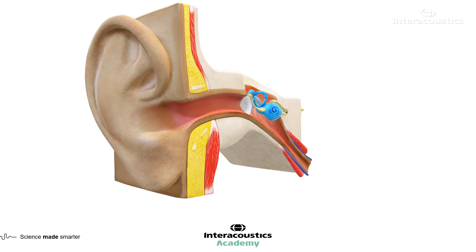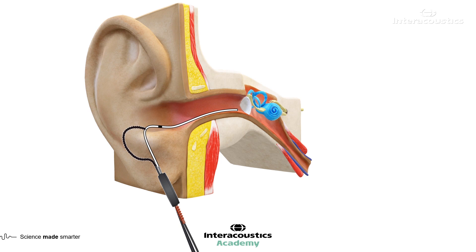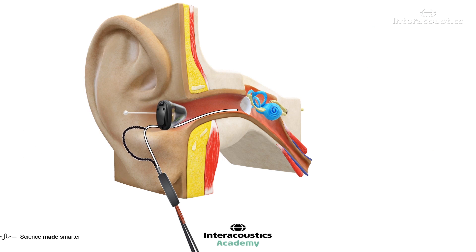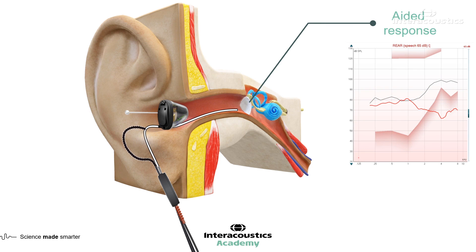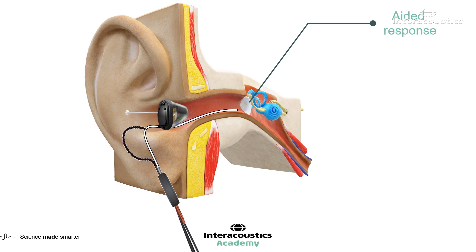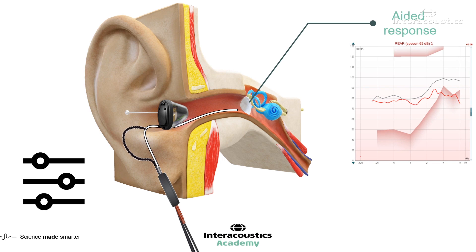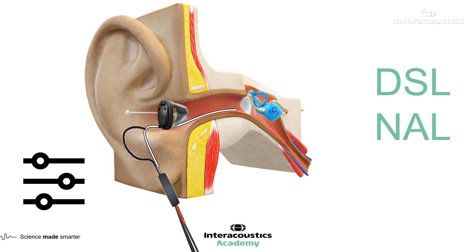We can use real ear measurements to establish the level of sound that reaches the eardrum specifically. We do this by placing a small tube that acts as a microphone, which gets calibrated to render it acoustically invisible. We can record this measurement unaided — which tells us the natural resonance of that person's ear canal — and then insert a hearing aid and measure again with the aid in place and switched on. If we aren't happy with the level of sound reaching the eardrum, we can adjust the gain and remeasure. This is where prescription targets come in; we recommend using DSL or NAL, as they have a large evidence base and provide the optimum amount of gain across the frequency spectrum.